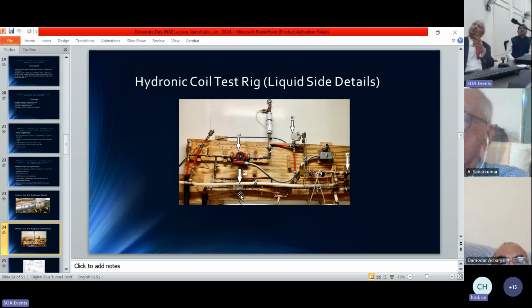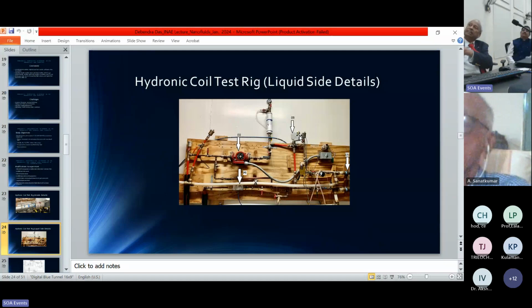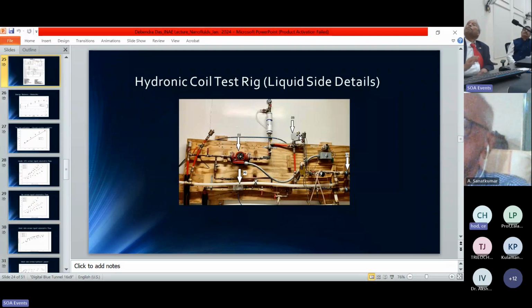This is our new liquid side, also on the wall, and on the top we have an air vent that allowed all the air bubbles to escape from the top. In the center we have the red circulating pump, and on the bottom we have the Omega fluid liquid meter. Then we have a heat exchanger here, and this heat exchanger gets much hotter liquid to heat the nanofluid in those loops. And then we have introduced some control valves so that we can control the inlet temperature to the coil to various realistic real-world temperatures, and get the performance of the coil.